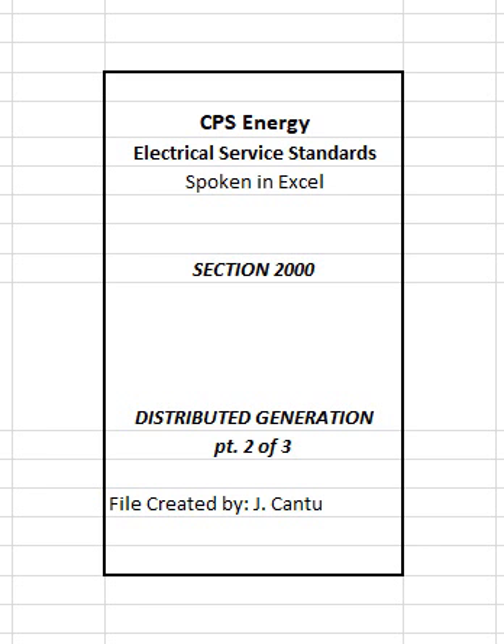H. Interconnection of PV system. Interconnection of a PV system shall be in accordance with the NEC and other applicable codes and shall only be done on the load side of customer revenue metering equipment. Refer to Figures 2002 through 2005. Raceways containing inverter output conductors shall be EMT for all above ground portions and shall not contain conduit bodies, LBs, or junction boxes unless specifically approved by CPS Energy's Electric Service and Metering Standards section. Exception: conduit underground shall be permitted to be PVC type. The portion of conduit extending above ground shall be permitted to be Schedule 80 PVC provided it is supported securely and does not extend more than 4 feet.